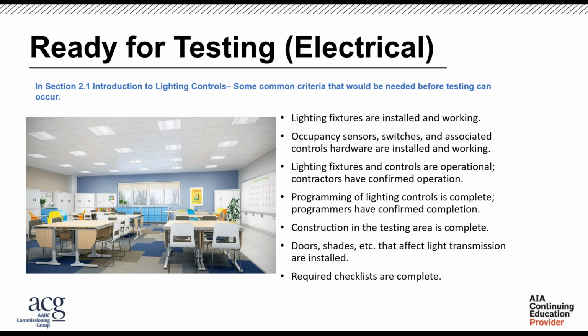One of the big things is that light fixtures are installed and working. There have been many times when all the light fixtures aren't in, and they still want you to test the programming. We need to have the final conditions: your occupancy sensors, your switches, all associated hardware installed and working. The fixtures and controls are operational, and contractors have confirmed operation. That's the big thing: before the commissioning provider gets out there, a lot of these operations should be confirmed. You want to make sure you're able to dim to 50%, or that if there's an emergency the lights come on to 100%.